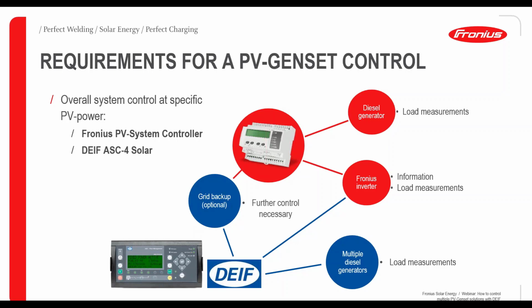In the red dots, we can see here the system controller from Fronius. We have here only the possibility to regulate one diesel generator. It's communicating with the Fronius inverter, and that's the one thing. With the blue dots, we now can see the DEIF solution. Both of them are possible to do a grid backup. It's optional also for Fronius. Also, both of them are communicating with the Fronius inverter. But in this case now, with DEIF, we are able to serve multiple diesel generators and therefore more complexity.